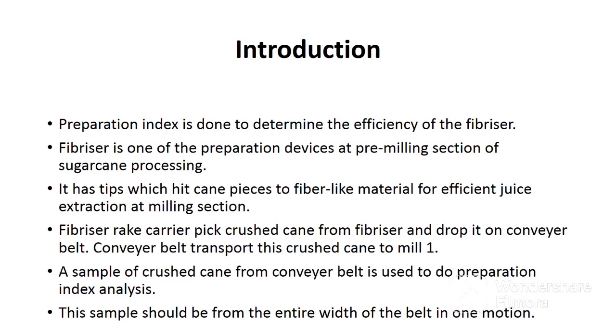The fibrizer is one of the preparation devices at the pre-milling section of sugarcane processing. It has tips which beat cane pieces into fiber-like material for efficient juice extraction at the milling section. The fibrizer carrier peels crushed cane from the fibrizer and drops it onto a conveyor belt, which transports the crushed cane to mill one at the milling section. A sample of crushed cane from the conveyor belt is used to do preparation index analysis.